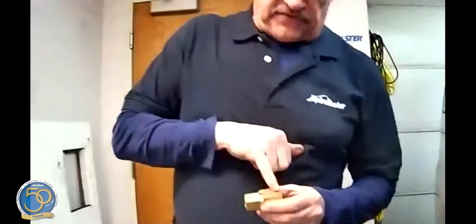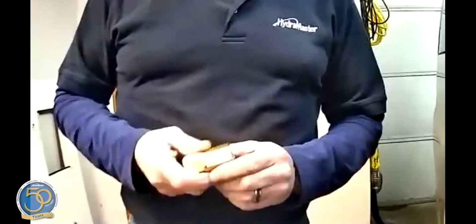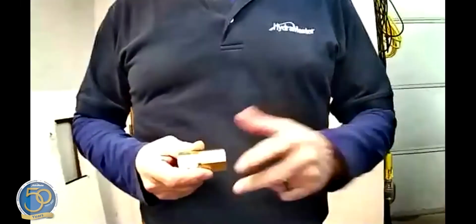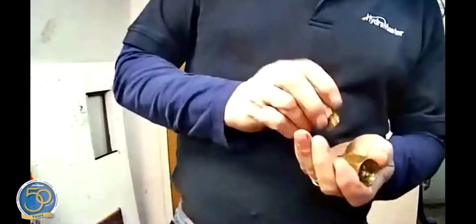So on the CDS, the differential check valve is located right behind the quick connect, the high pressure manifold. Let's see, kind of hard to see here. It's this guy, hex-shaped brass 2-piece body. And here's a good example of it right here. What this has is a chemical differential check valve, a 1-way check valve. And we're bringing the high pressure water from the heat exchangers into one end of it. And it goes through it, but on the innards of this, we have a spring and a check ball. And what that's doing is giving us resistance. So this is considered a 100 PSI check valve. We use a small spring and a small check ball on the interior of it.